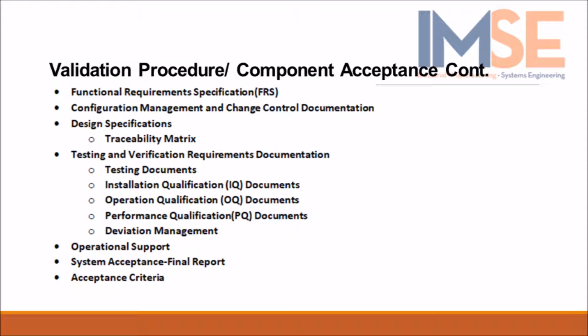Configuration management and change control documentation. Change control is a formal process by which qualified representatives of appropriate disciplines review proposed or actual changes that might affect a validated and/or approved status. The intent is to determine the need for action that would ensure and document that the system maintains this status. This process documents the pre-implementation changes and post-implementation changes.